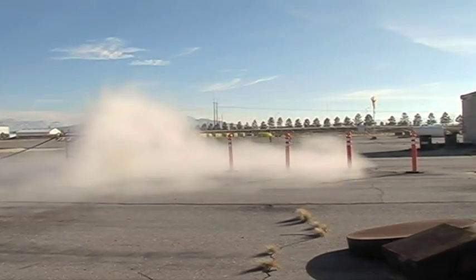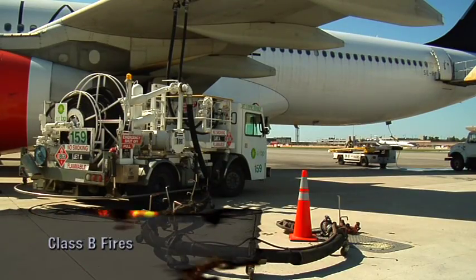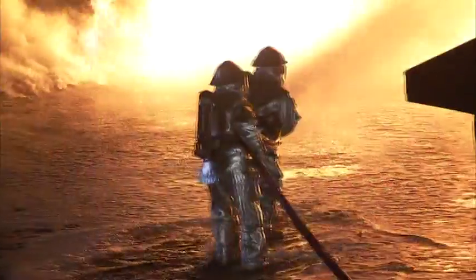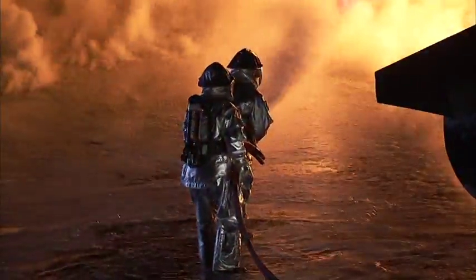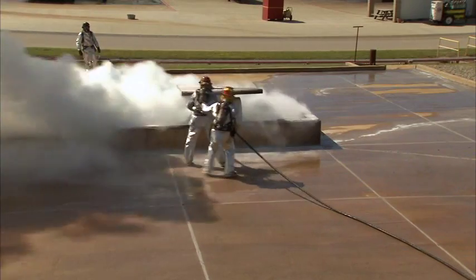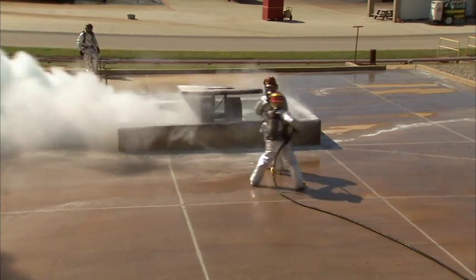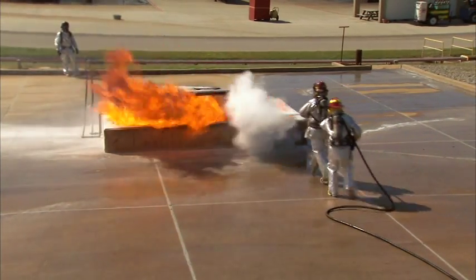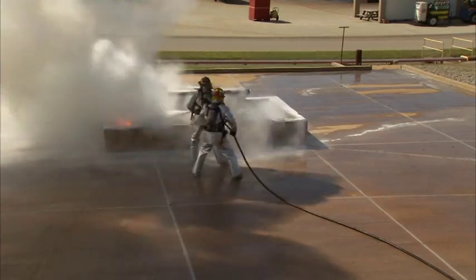If the vehicle is equipped with a piercing nozzle, approved halogenated agents such as Halon 1211 or Halotron I may be discharged into unoccupied aircraft compartments. The greatest fire hazard at airports is aircraft fuel, which is a flammable liquid or gas — a Class B material. Foam is the agent of choice for Class B liquids, since it not only extinguishes the fire but prevents re-ignition. However, foam is ineffective in fighting pressure-fed gas fires. Dry chemicals and clean agents will extinguish Class B liquid fires but will not prevent re-ignition. Dry chemicals and clean agents are the agents of choice against Class B gas and three-dimensional fires.